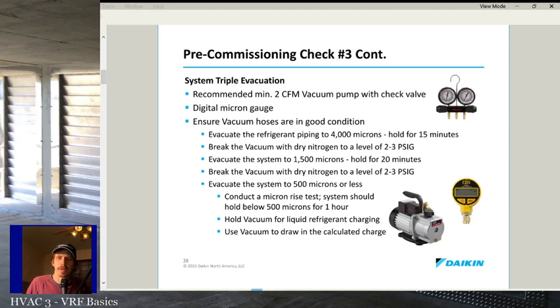So once you get all the piping done and installed correctly, you want to evacuate it. It is important to make sure that you're on this system. They recommend on VRF a 2 CFM minimum vacuum pump. The CFM of the vacuum pump is not as important as trying to make sure that you have good hose connections. Hopefully a good vacuum manifold, not a refrigerant charging manifold, unless it's a good refrigerant charging manifold that's made to also be used for evacuation purposes.